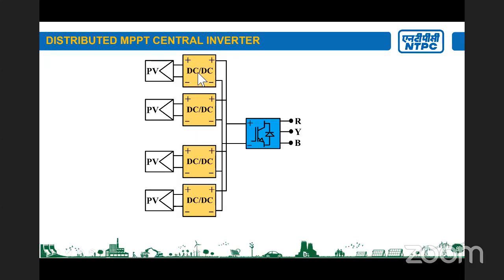The DC-DC converter will operate the PV at its maximum power point, and it will be a true kind of multi-MPPT configuration. Then the DC-DC converter outputs are again paralleled at a central inverter, which converts DC to AC. I think this configuration may come in the future, because now the central inverter people are shifting to string inverters, but because of the size limitation in the string inverter, the central inverter is still preferred. With this configuration, at the field side you have an MPPT DC-DC converter, and at the main common point you have a central inverter.